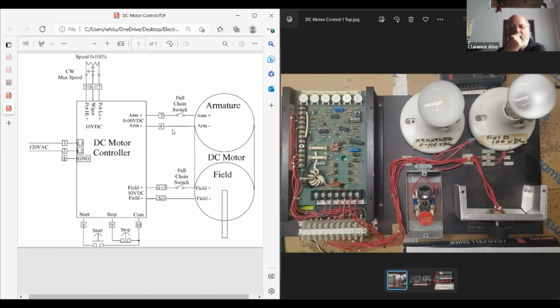Okay, let me pick on this a little bit. I press my start button here, and I'm sitting in the middle for 5 volts. I'm expecting to see my light come on real high, or at least somewhat, because we've got half speed, and my field voltage comes on. But I can see my light's not coming on. I just got done proving that my hot signal made it to my DC motor control, and I know I got voltage coming in because I've got a power supply here.